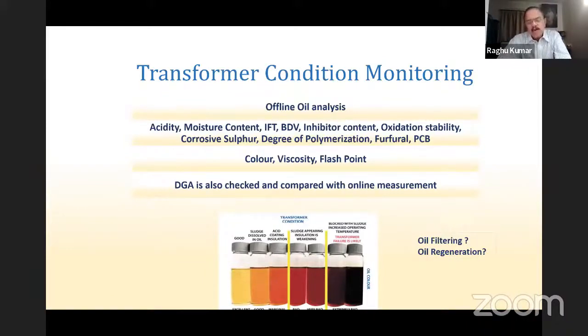How do you reclaim the oil? The oil can be filtered, yes, and filtering can remove the gases and the moisture. IFT can be improved, BDV can be improved, but it cannot change the color and it cannot change the acidity. These two cannot be reversed by oil filtering. So what is the solution? There are two solutions. One is you replace the oil completely. The second is called oil regeneration.